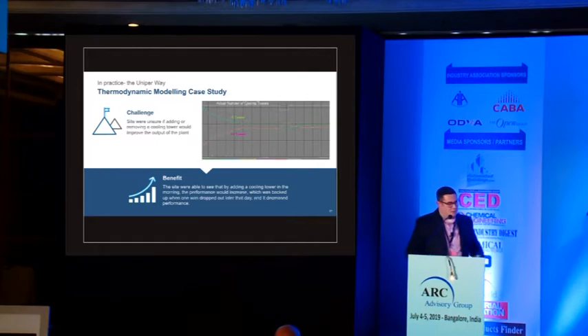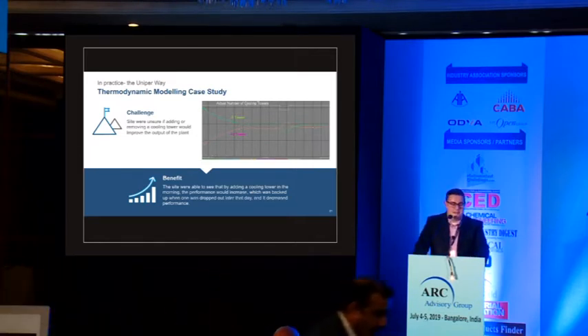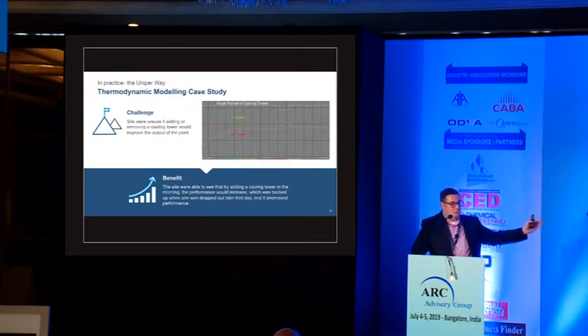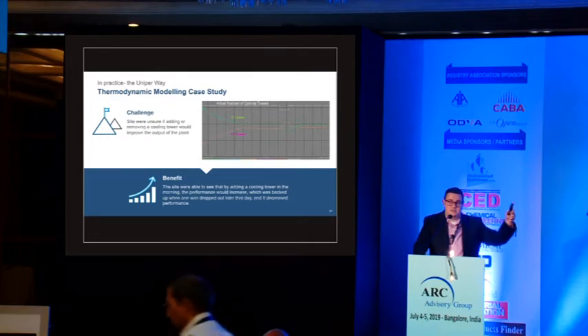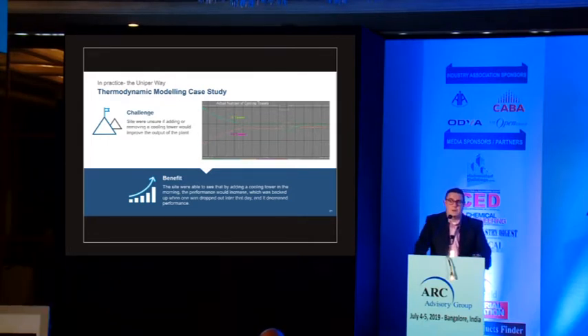A couple of case studies where we've seen real benefits. In one case, the site was unsure if adding or removing a cooling tower would improve output. We were able to show that adding a cooling tower in the morning increased performance, which was backed up when one of the cooling towers was dropped later in the day - shown by the white line at the top - which decreased performance overall. So they were able to make that assumption and check it in the system before actually making the change on the plant.